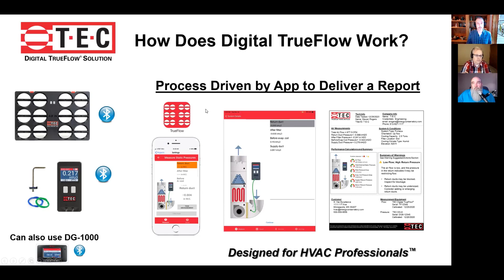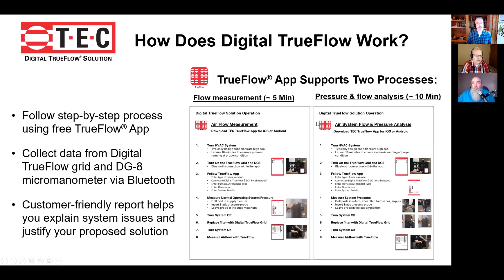The idea is the app drives the entire process. It helps you make the right measurements in the right order. It collects that data. It helps analyze that data and make suggestions about actions that should be taken if the airflow doesn't look good. So there's two main methods or processes that you can do with the app. One is to measure flow only, whether that's just by your own commissioning standards or to do a grading per ACCA ResNet 310. And then there's also a pressure and flow analysis. That's the one we think delivers the most value.